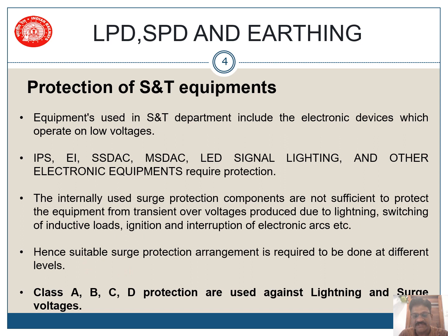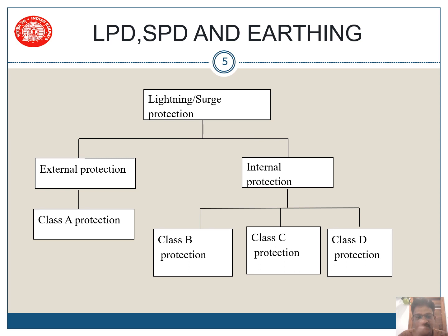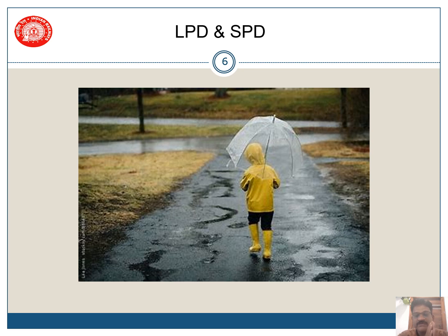Hence, suitable surge protection arrangements are required at different levels. Different levels of protection are required for these equipments. So generally they are classified as Class A, Class B, Class C, and Class D protections against lightning and surge. If you classify lightning and surge protection devices, you can say external protection and internal protection. External protection is called Class A protection, while internal protection can be Class B, Class C, and Class D. All these equipments make up how this system works.